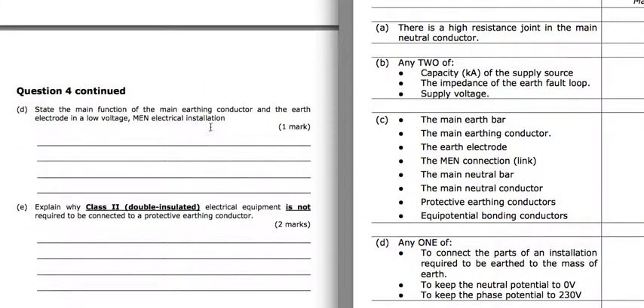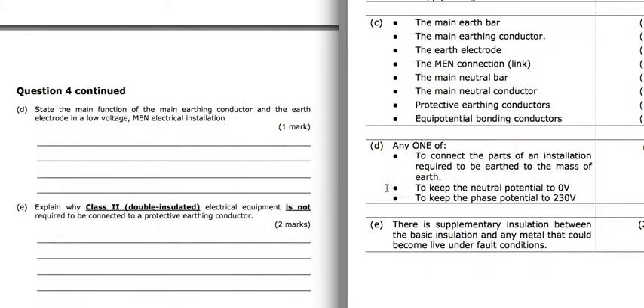The main function of the main earthing conductor and the earth electrode in a low voltage MEN installation. So they give you a couple of answers there. Connect the parts of the installation required to be earthed to the mass of Earth, to keep the neutral potential to 0, and to keep the phase potential to 230 volts. So we've seen that question in a slightly different way, but the earthing is all about keeping that neutral at 0 and the phase at maximum of 230.